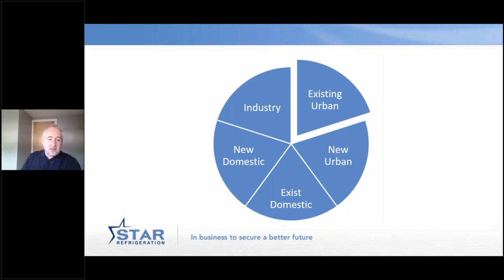In the existing domestic sector - my house is a 1950s bungalow on the south side of Glasgow - I've got a heat pump and I'm managing to heat even my not terribly well insulated building, using a heat pump operating at a slightly higher temperature, typically between 50 and 55 with a ground source. I'm able to heat my house even through the winter, with no gas connection anymore whatsoever.